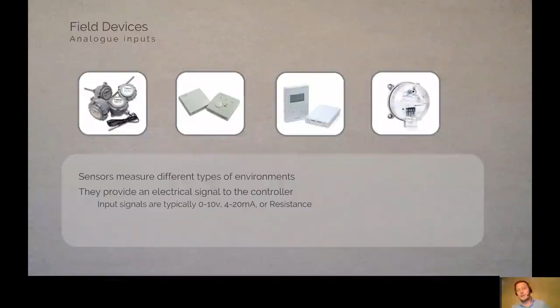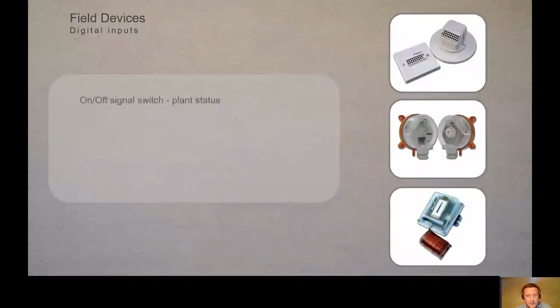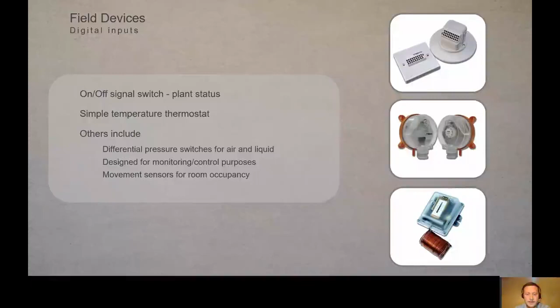There can be lots of different types. As I say, 0 to 10 volts, you can have current, or you can have resistance for that, and then we'll convert that, as I say, into a meaningful value. We also have digital. These are on-off statuses, so things like presence detection, differential pressure. So if you're reading the pressure value, it's either above pressure or below pressure, so it's only binary. Things like frost conditions, as an example, a frost stat on a heater battery, it's either in frost or it's not above a certain value.